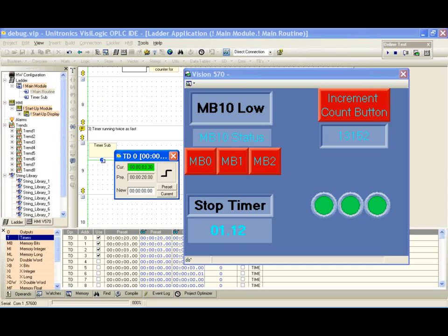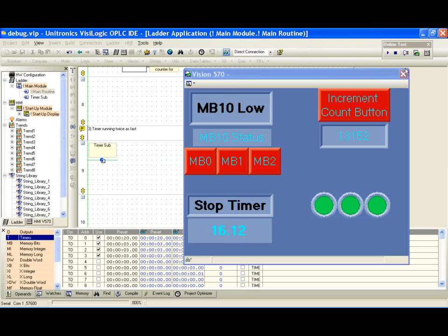Okay, Barry, thank you. So Barry says that it's being activated twice, 2 coils. That is correct. The proper use of a timer is to activate it once per scan. If we activate it twice, we'll count twice as fast, three times as fast, and so on.